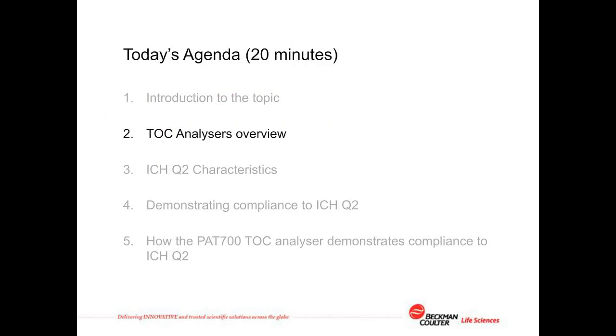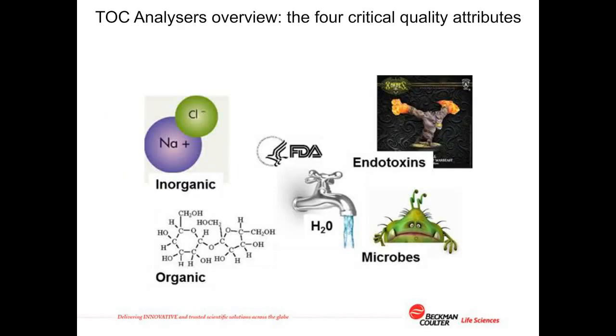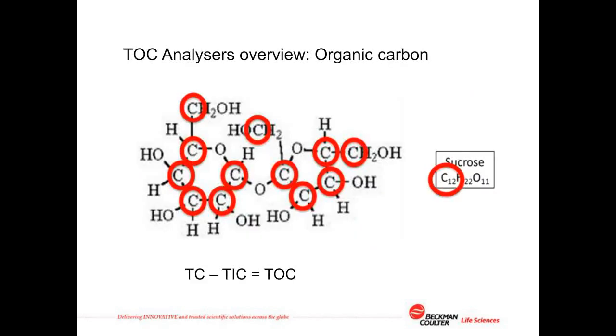TOC analyzers measure one of the four key critical quality attributes mandated by the pharmacopoeias. The other three are inorganic contaminations, typically measured using conductivity; endotoxins, which are substances that can act on the patient's hypothalamus and cause fever; and microbes, which if injected into a patient could cause infection. TOC analysis is a nonspecific test — it is simply a measure of the amount of carbon found in the organic compounds in the water. It cannot tell you what type of organic molecule is present.